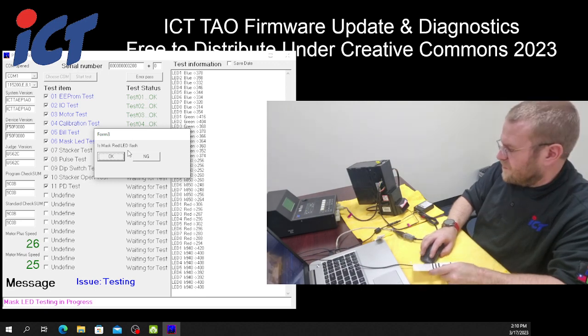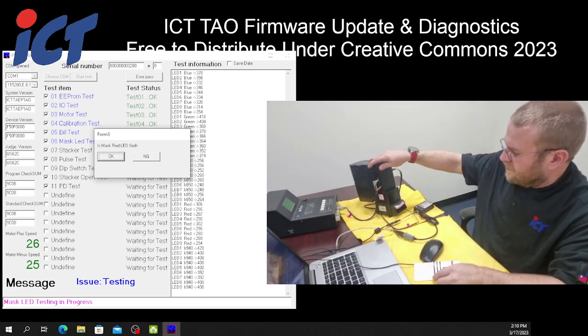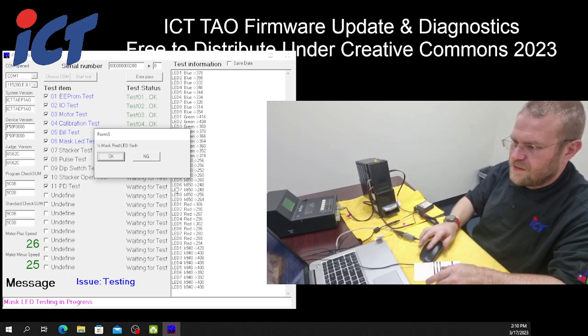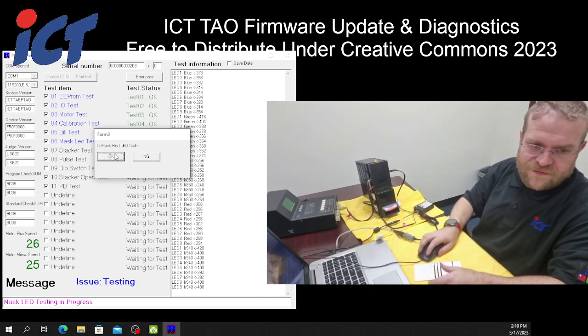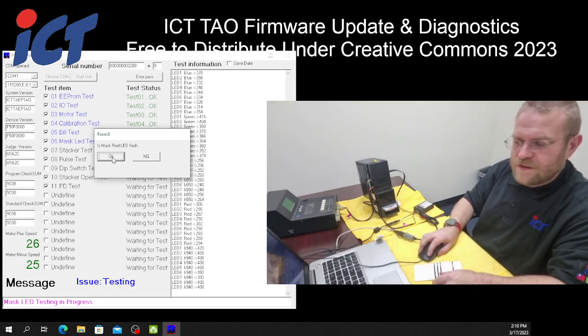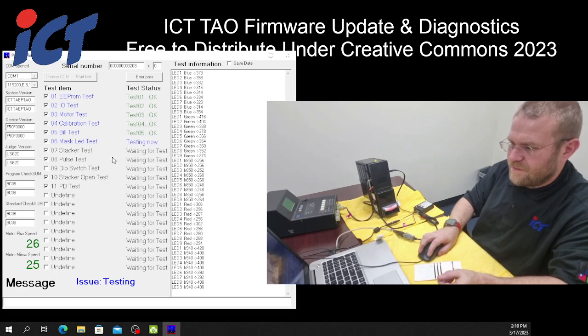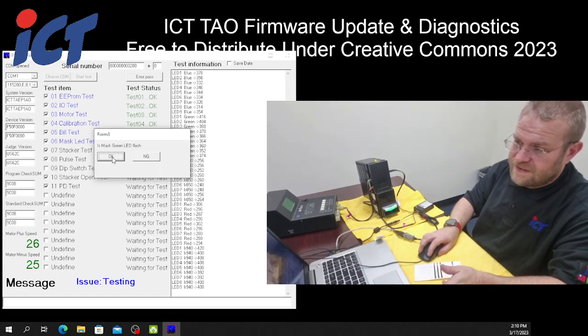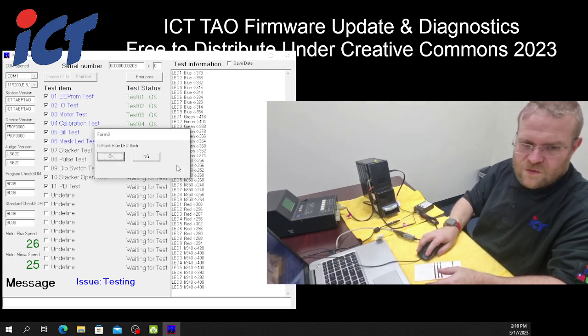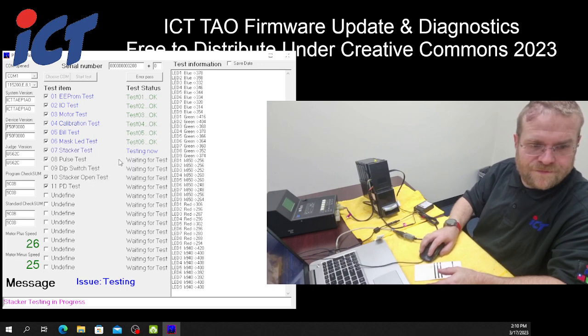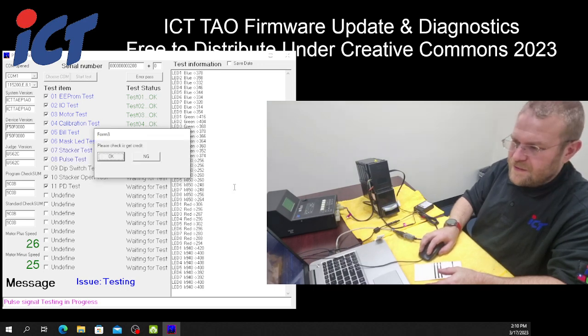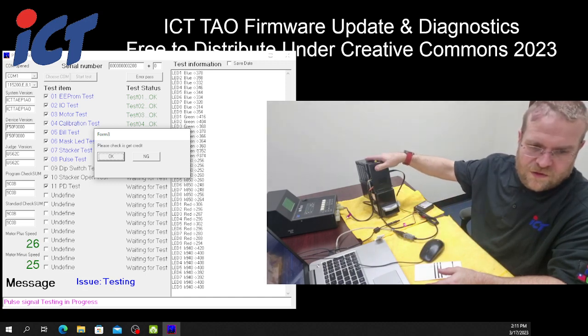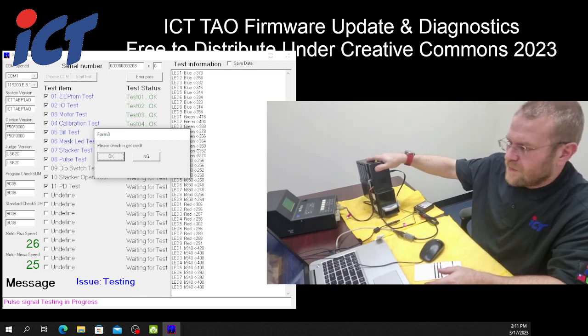In this next test, it's going to ask if your front bezel is flashing red. Answer that appropriately. If it is, hit yes or okay. If it's not, you would hit not good. So since this is flashing red, you hit okay. It will then go to the green test, which is okay, and then to the blue test, which also is okay. Next test will stack once to test the stacker motor.